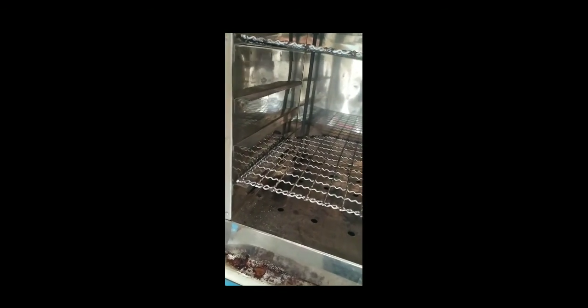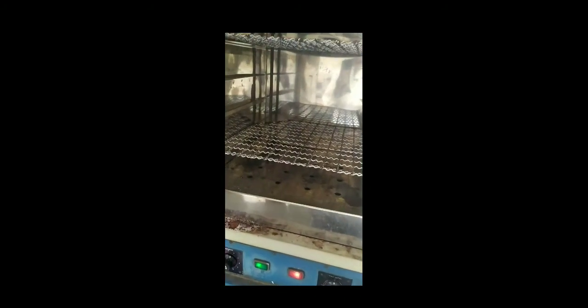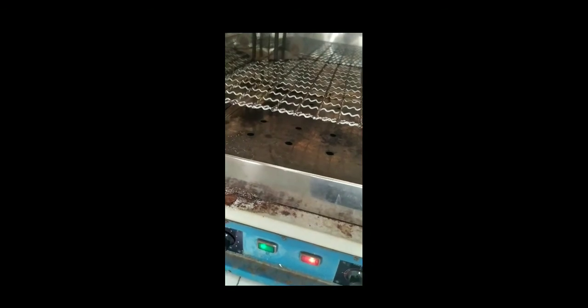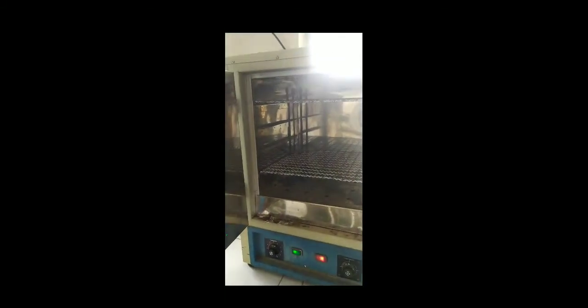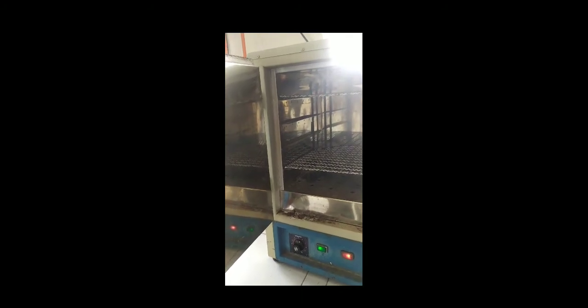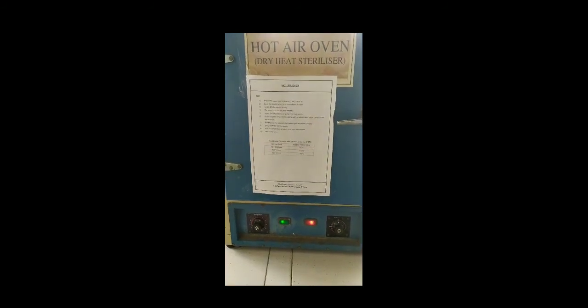These are the baskets. They hold the material which you have to sterilize. The heater or heating coils are present underneath this. This is the air vent. This is the side from which we can insert our thermometer for measuring the temperature. The temperature and time vary from material to material. You can use this sterilization method for various materials like glassware, metals, and dry powders or other dry materials. There are some SOPs or standard operating procedures which you have to follow strictly. This is the dry heat sterilizer or hot air oven.